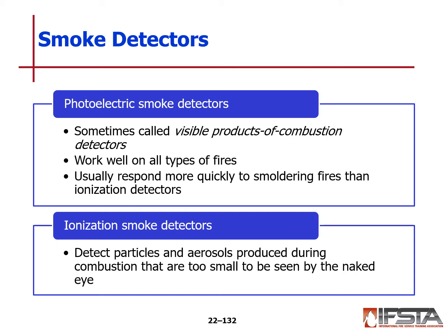With your smoke detectors, these could be photoelectric detection, sometimes called visible products of combustion detectors. They work well in all types of fires, and usually respond more quickly to smoldering fires than an ionization type detector. So our other type is ionization. These types of detectors will detect particles and aerosols produced during combustion that are too small to be seen by the naked eye. So a lot of these, even your smoke alarms, the detector in those alarms in the residence have an ionization process. You'll not see any visible smoke, but it can still set the alarm off.